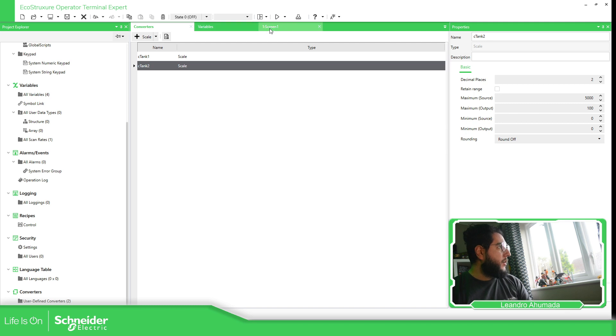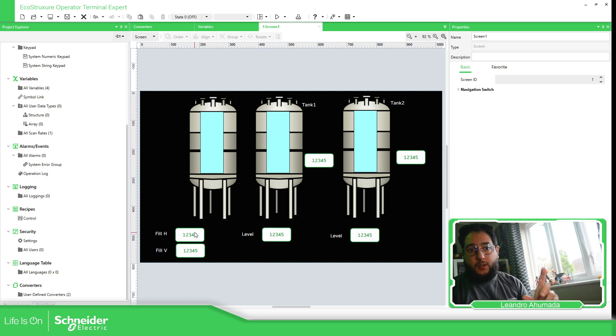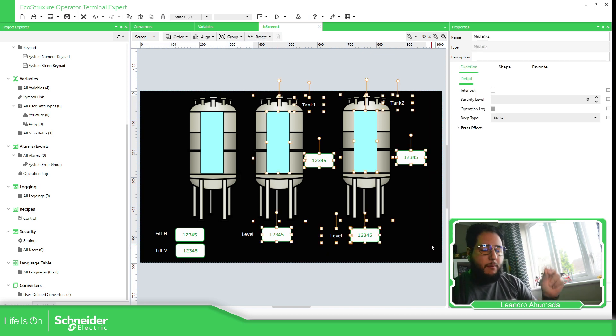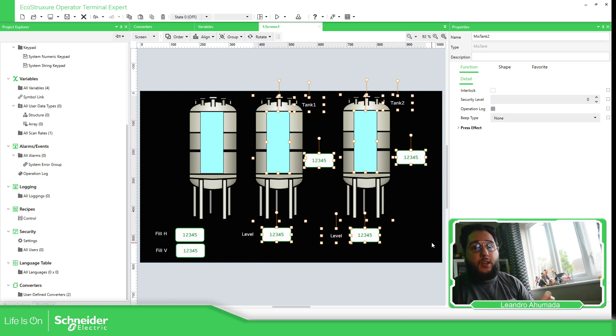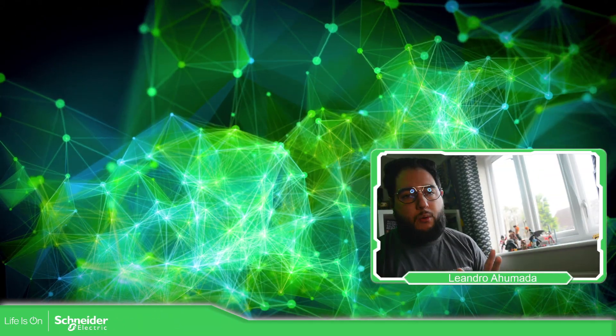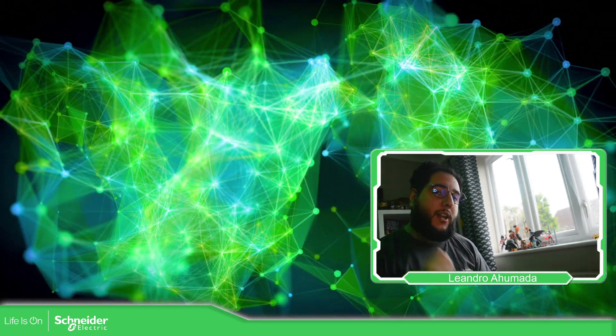So this is how you can work with the fill property of the object. If the variable is already in percentage, you can use it directly. Otherwise, what you need to do is use a converter to scale the tank level value to 0–100%. There is no need to have an additional variable on the PLC with the percentage — if you want to have it you can, but it's not necessary. So thank you very much for watching this video, and I'll see you on the next one.